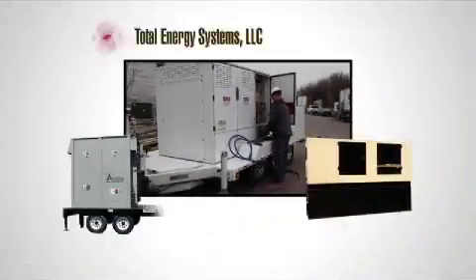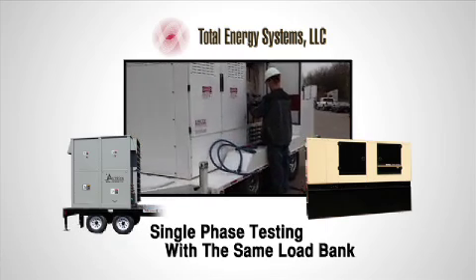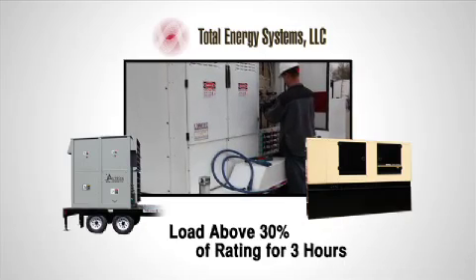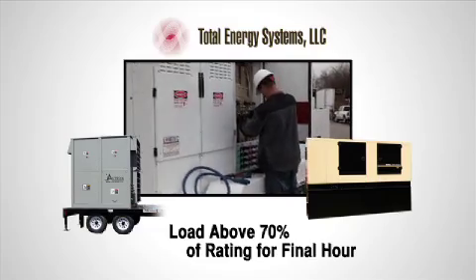Load banking can be part of the usual planned maintenance contract. Our technicians carry out the recommended NFPA 110 4-hour test, which calls for a load of at least 30% of rating for 3 hours and above 70% of rating for an additional 1 hour.